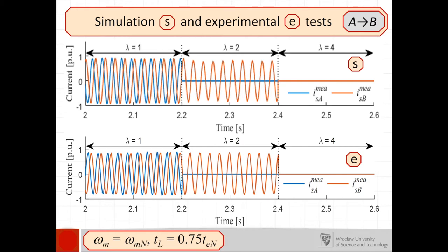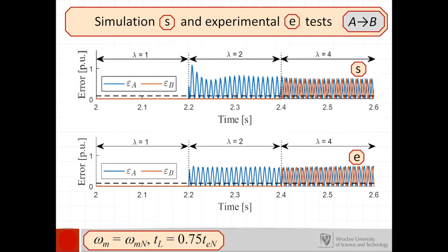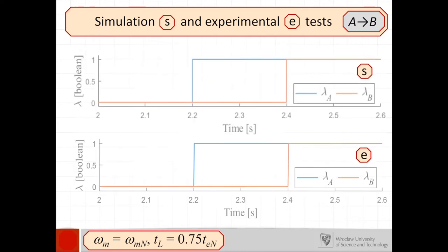The fault occurred in the steady state and as can be seen here, epsilon coefficients very quickly exceed the threshold value, established in both cases at 0.1. This allows very fast current sensor fault detection in phase A and next in phase B.